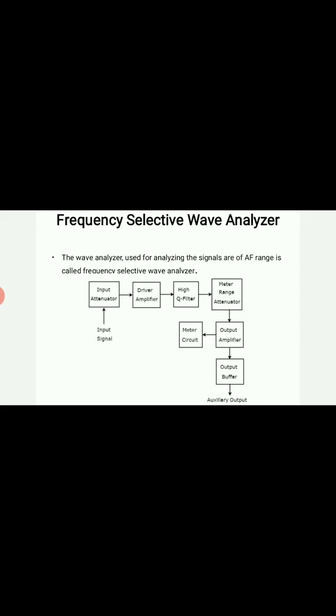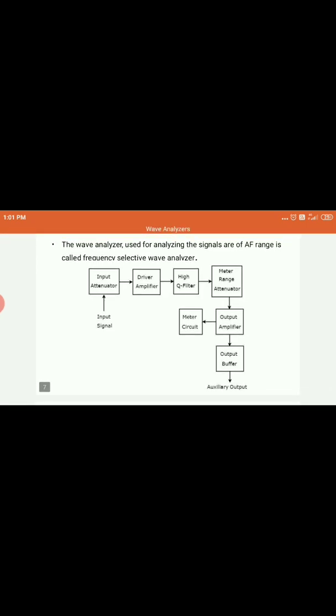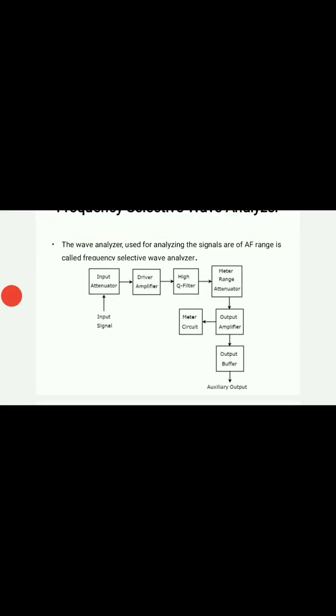The signal, after passing through the high Q filter, passes into the meter range attenuator, which attenuates the signal into the meter range. It then passes through the output amplifier, which amplifies the signal if required, into the meter circuit and the output buffer. You can take auxiliary output from the output buffer, and the signal from the meter circuit is used to measure.